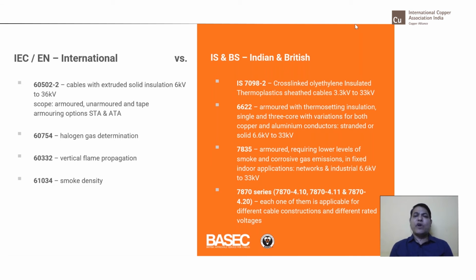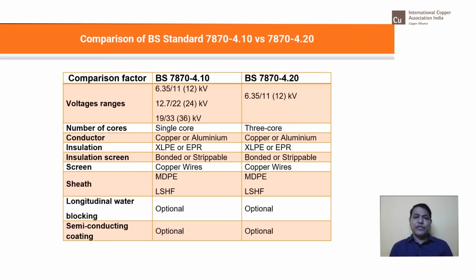They don't mix everything in one standard, because that often causes confusion, as happens with the IEC standard. People make anything and everything, a design not experimented or tried, because a customer asks for something for a certain application, and they are free to do that. But whether the design really works, is tested, or is in commercial use, nobody knows. So there is some risk with that standard, but otherwise it gives very good flexibility. Whereas the British standard clearly gives everything, from conductor to dimensions to thicknesses, and the tests are very, very clear. So 7870 is normally used by UK utilities, by generation utilities and distribution utilities.